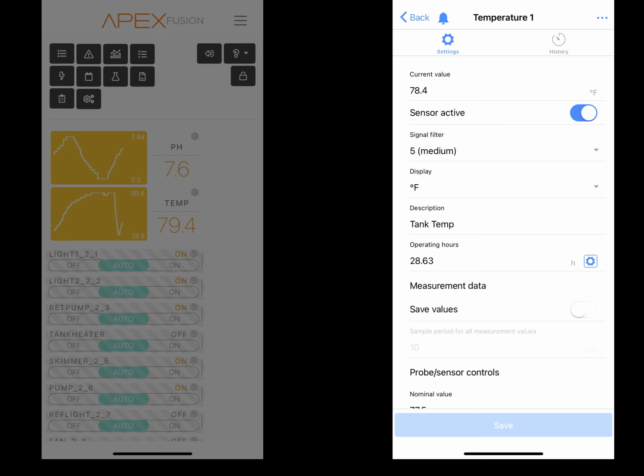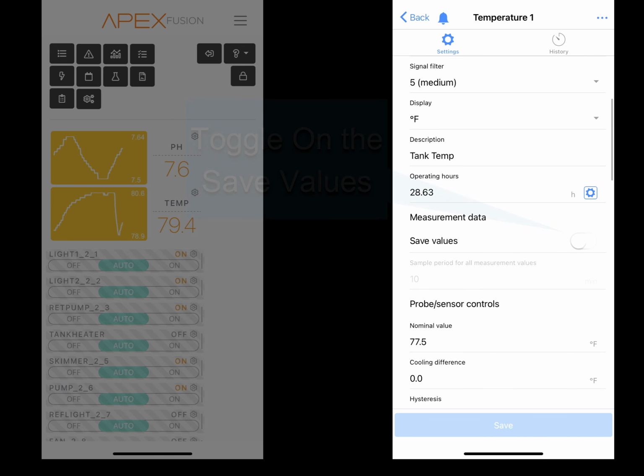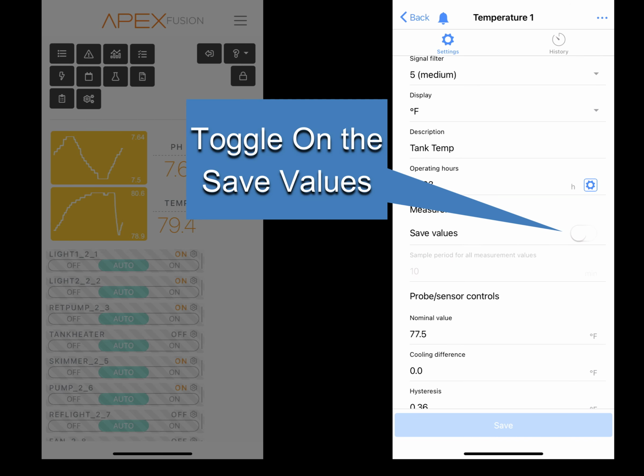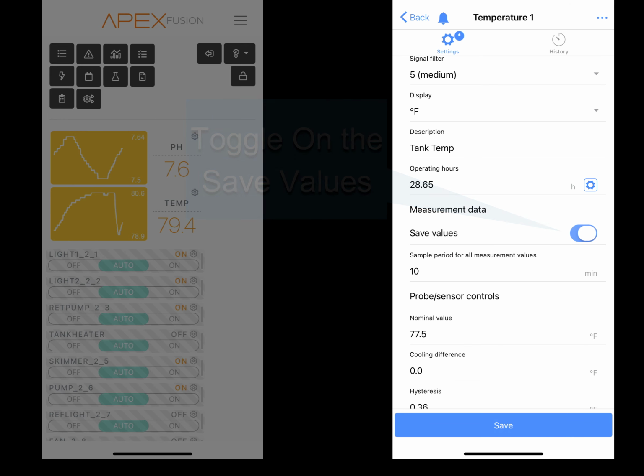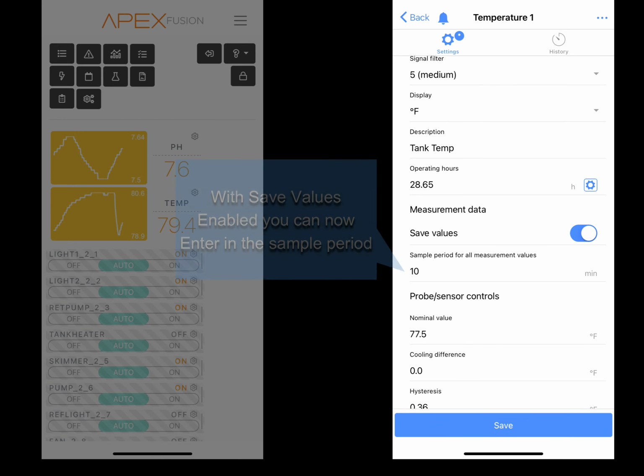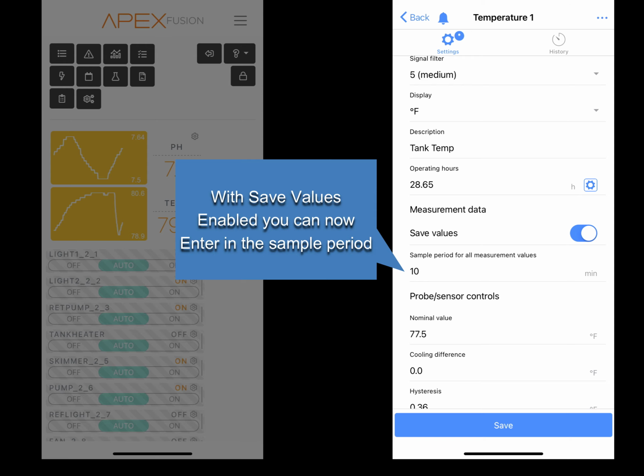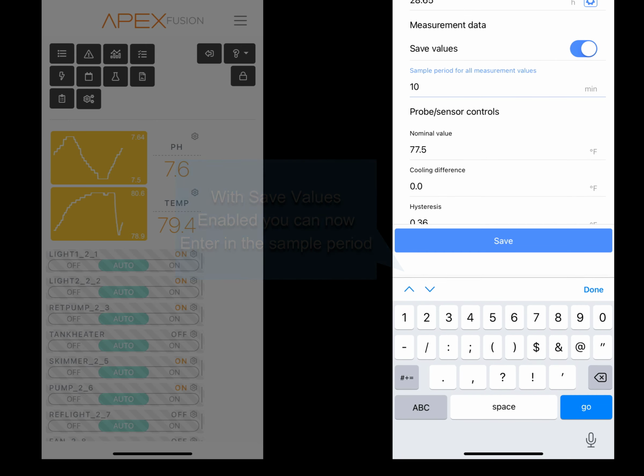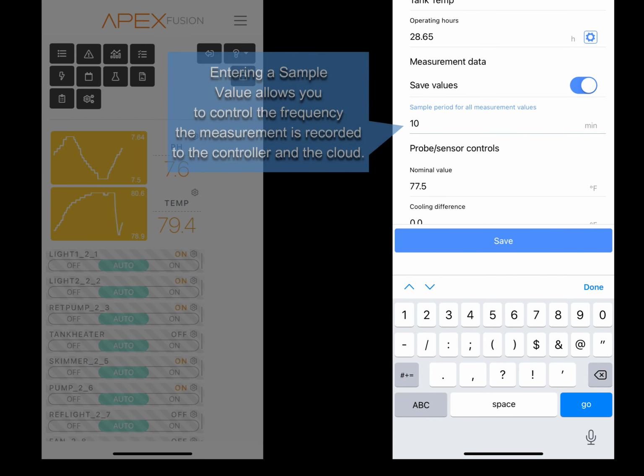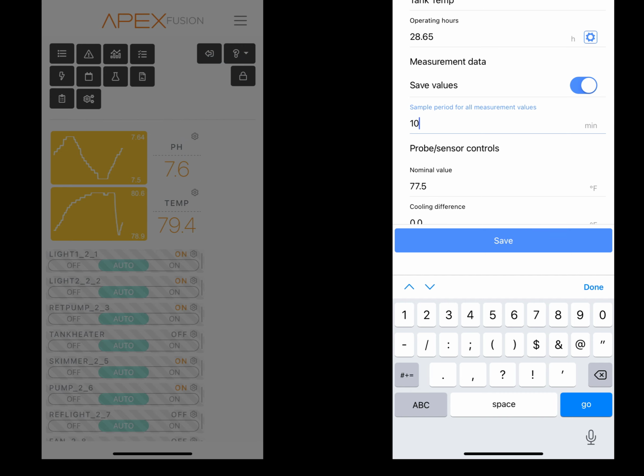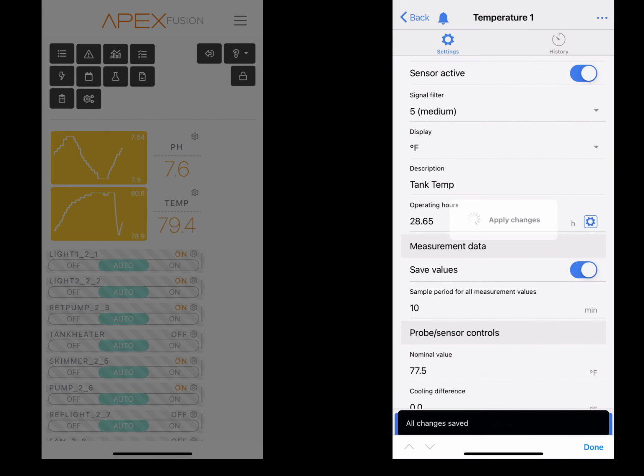Scroll down to the measurement data section and toggle on the Save Values feature. Upon doing this, you can now enter in a sample period for the measurement interval. By default, it's 10 minutes, but you can change it if you wish it to record every 5 minutes or every 15 minutes. You can enter in the value that you see fit. I'm going to leave it at 10 minutes, and I'm going to choose the Save button. What this does is saves the settings to the controller.